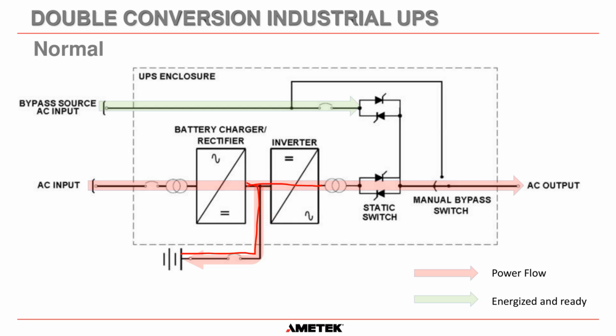And then that DC also goes into the inverter, directly into the inverter, not through a DC to DC converter. And then that inverter changes the DC back into AC. That goes through an isolation transformer and then into our static switch. So remember on the previous commercial UPS, that was a contactor. In this system, we have two static switches. So this static switch is always on in normal operation, and then the power flows out to the AC output to the loads. Okay. And once again, our bypass is present at the bypass static switch, but the bypass static switch is not on. It's just waiting for a signal just in case the input to this static switch fails.